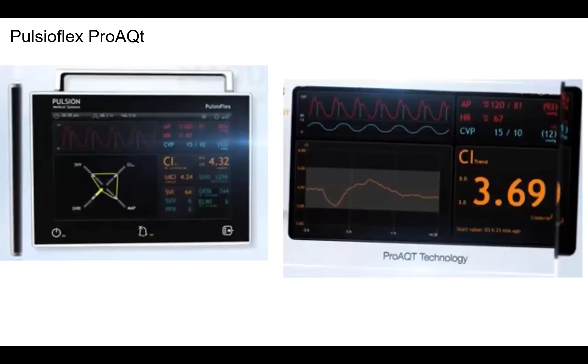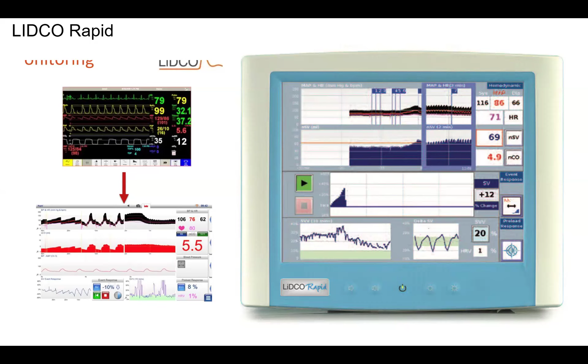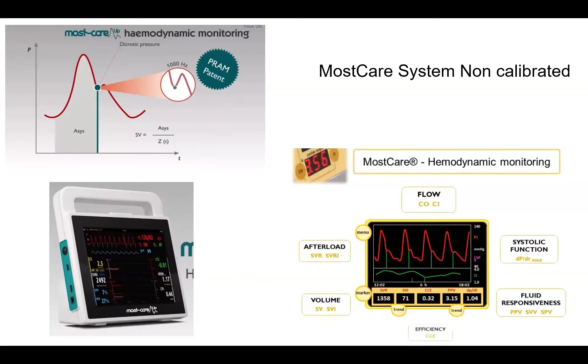So this is a PulsioFlex, which uses the ProAQT technology. This is a LiDCO Rapid. This uses a pulse power analysis technology. The pulse power analysis does not use the morphology of the AP waveform to estimate cardiac output. It translates the original AP signal into a standardized volume waveform based on the assumption that arterial compliance changes as AP changes. The MostCare system, which is non-calibrated, uses the PRAM or the pressure recording analytical method to analyze the AP waveform over the whole cardiac cycle and identify specific parts of the AP waveform that only last for a few milliseconds, called the points of instability.